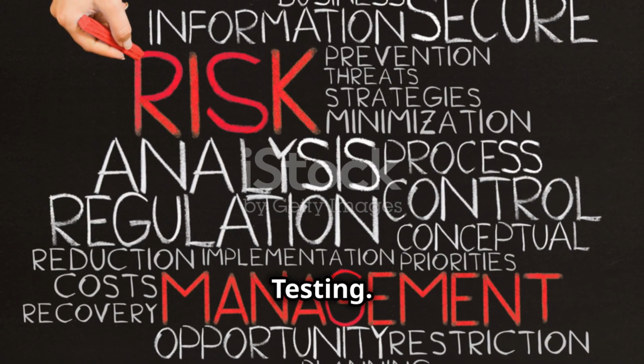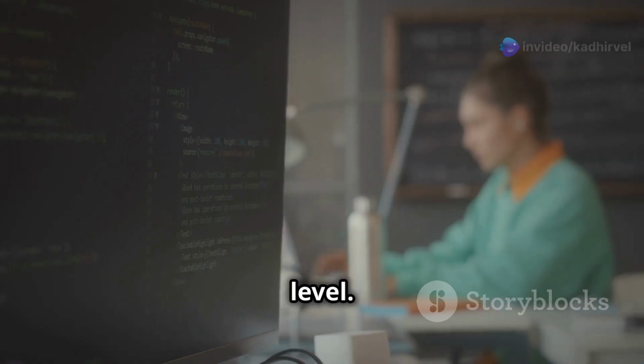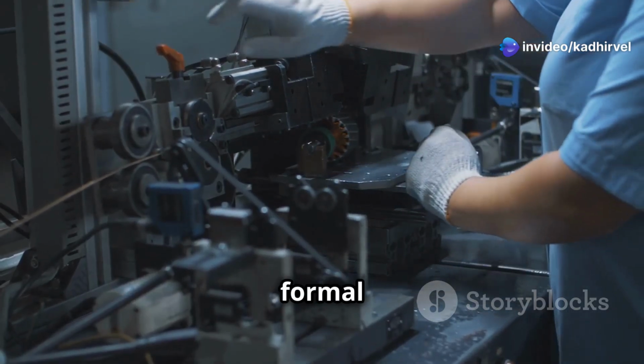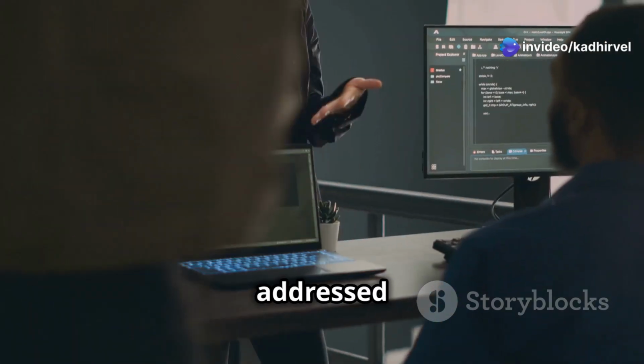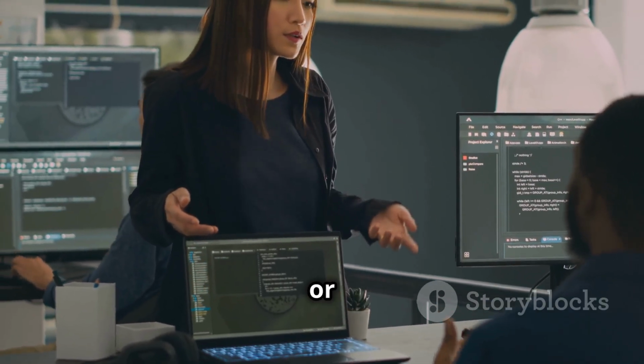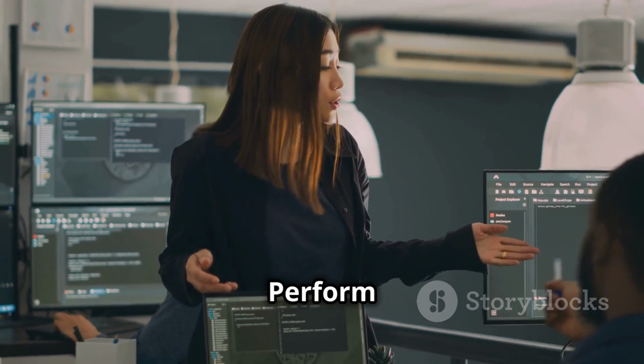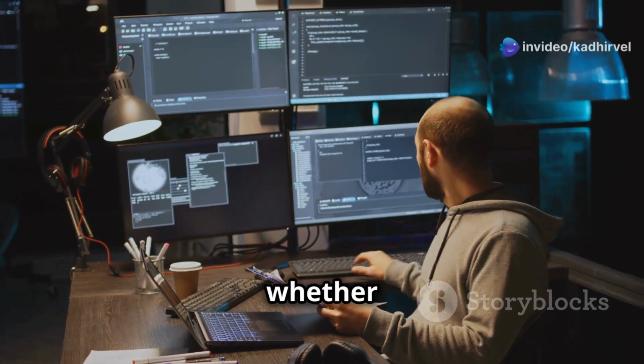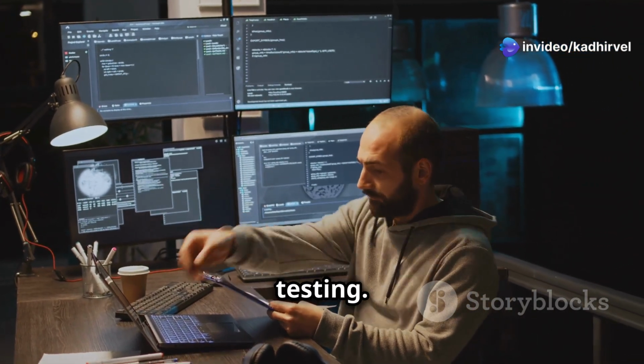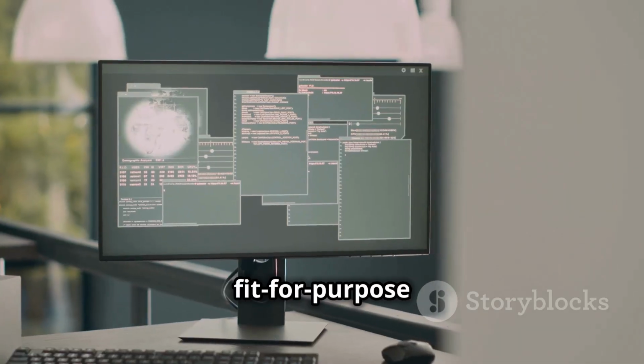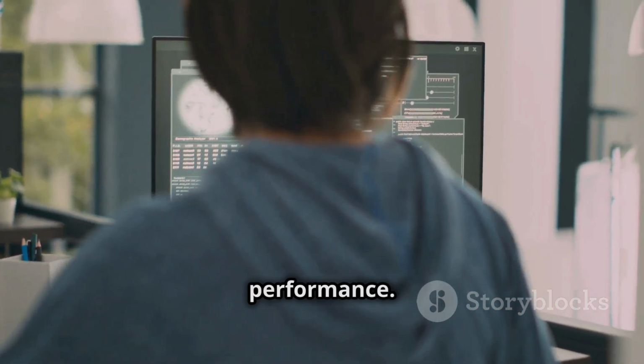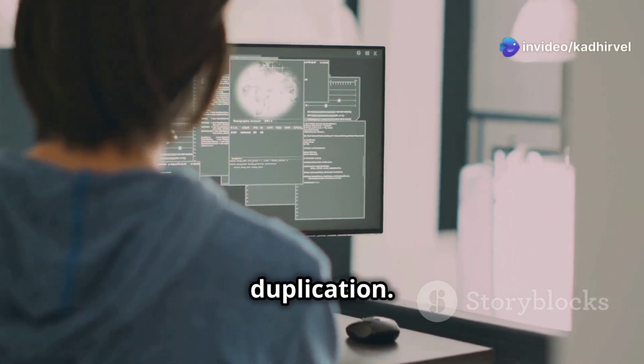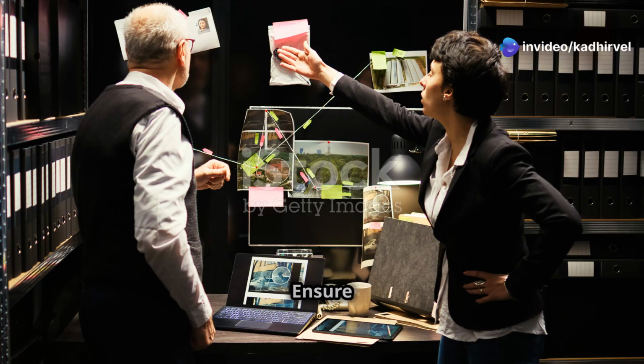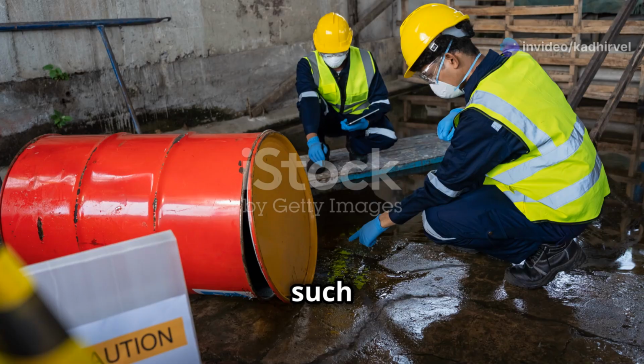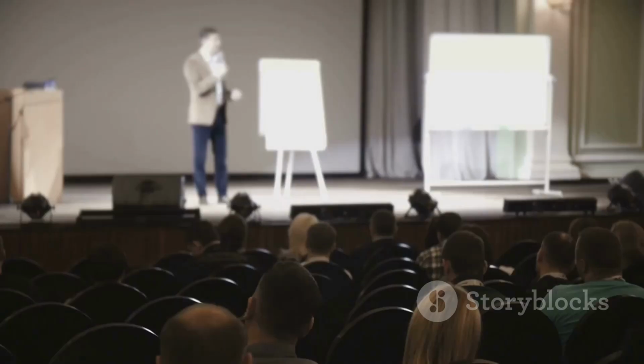Third, select appropriate testing. Based on the risk, determine the testing level. High risk requires scripted testing with formal protocols. Medium or low risk can be addressed with unscripted testing, ad hoc testing, or sometimes no testing at all. Fourth, perform testing. Use modern testing methods, whether scripted, unscripted, or automated testing. Capture results to demonstrate assurance. Fifth, document the results. Create fit-for-purpose documentation to ensure confidence in software performance. Avoid unnecessary duplication. And finally, review and approval. Ensure compliance with applicable regulations, such as FDA 21 CFR Part 11.